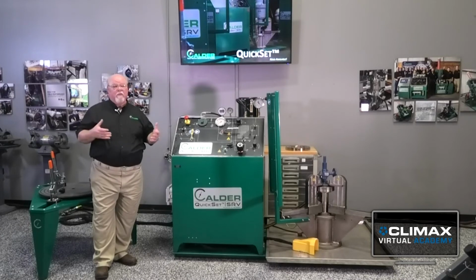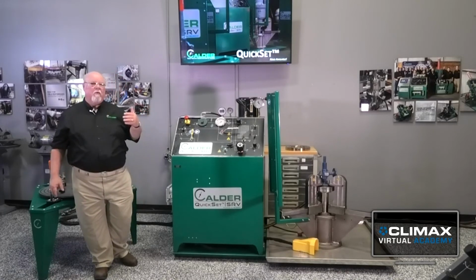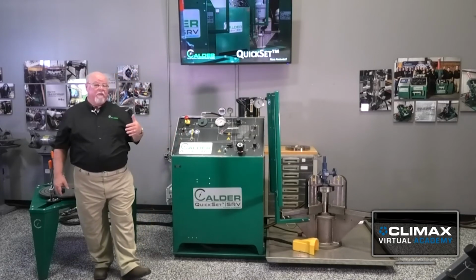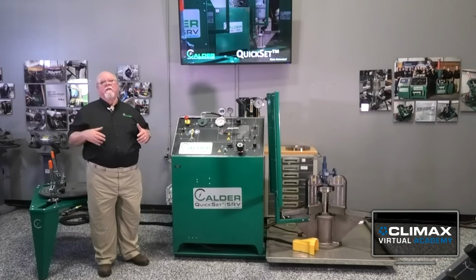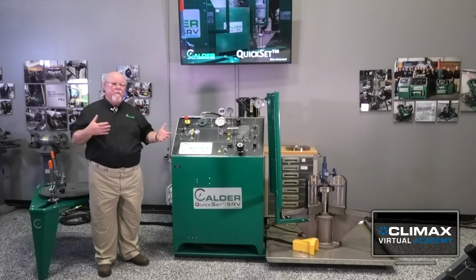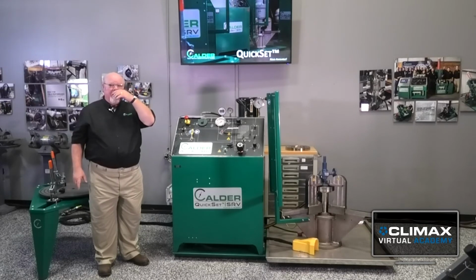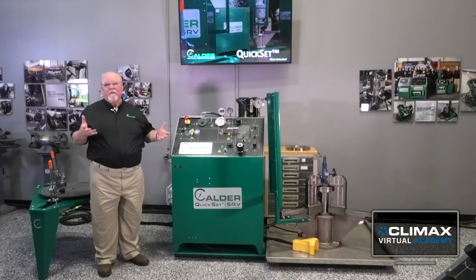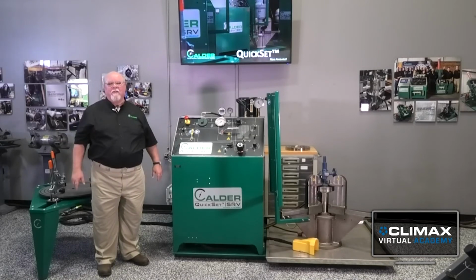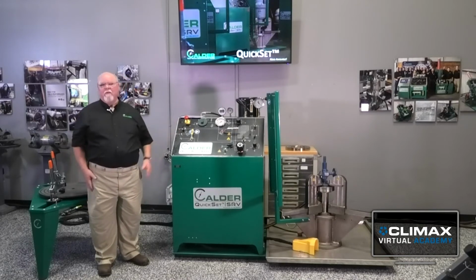They were setting the simmer point, and so as designed, these spring-loaded, metal-seated valves are not guaranteed to be seat tight above 90%. In fact, API 527 allows them to leak above that point, so they can start leaking at 90 to 100%. So if you don't have enough volume and enough feed to the test port, the volume leaks out before you can get enough to get it to pop. So often when you would see field test stands, they were setting the simmer point. They were trying to determine where it was starting to leak, as opposed to where it was at testing. A common method used to be to run the lower ring up and try to close up that annular space. There's some discussion as to whether that affects the accuracy of the test or not. So if you provide enough volume, then you don't have to do that.